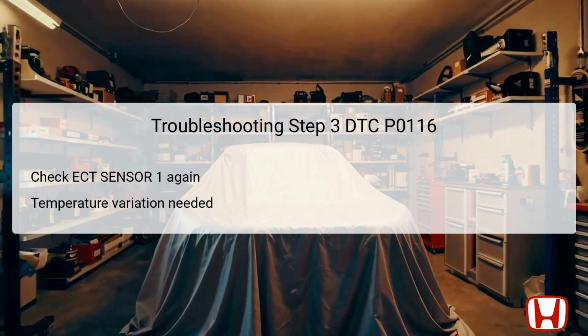If such a change is observed, this suggests that the ECT sensor or its circuitry is functioning properly at this moment. However, if no significant change is detected, further investigation is warranted. This step is critical, as it helps identify whether the ECT sensor's responses are within expected operational ranges or if they remain static, indicating potential intermittent failure of the sensor or wiring issues.